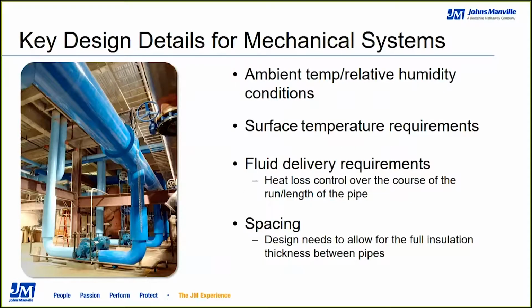So what are some of the key design details for mechanical systems? First, you want to consider ambient temperature and relative humidity conditions surrounding the system. For instance, a system running 350 degree steam in a 75 degree ambient temperature space with low humidity is going to perform much differently than a system running domestic cold water in a 90-degree ambient and high humidity type environment.